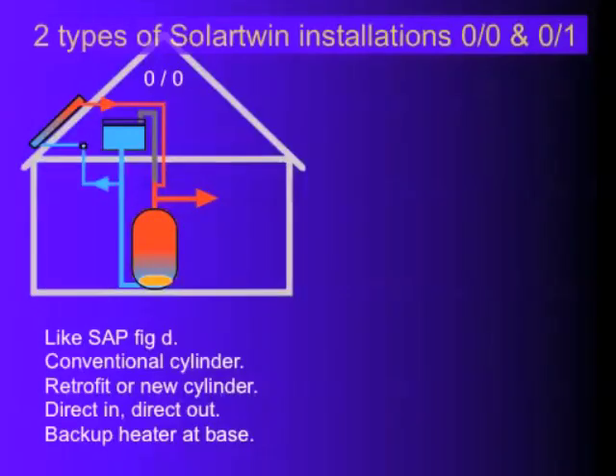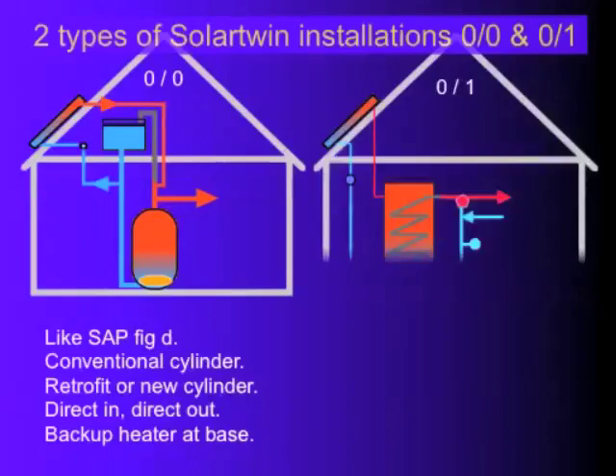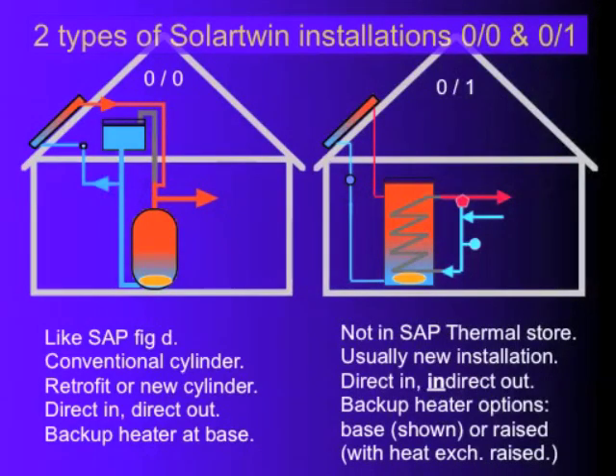If you want to look at two solar heating systems that Solartwin do: here's one — it's a retrofit to an existing hot water cylinder — and here's another one with a thermal store, both of which have a large volume of water going to and from a solar panel. The one on the left, referred to as nought-nought, has the water being heated direct by the solar collector, hence the nought, and the same water comes straight out from the cylinder, which is a nought. The nought-one refers to one heat exchanger on the way out because there's a large mains pressure heat exchanger.